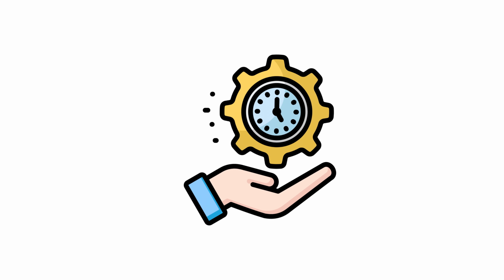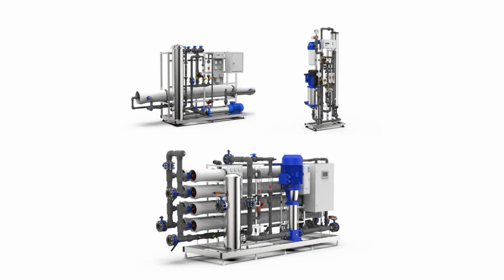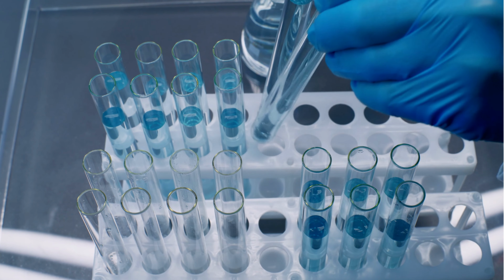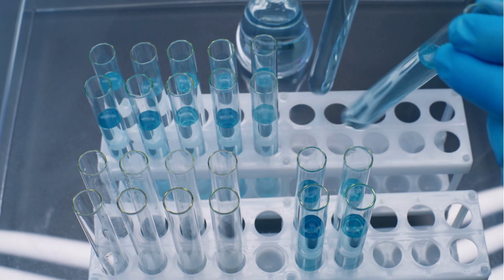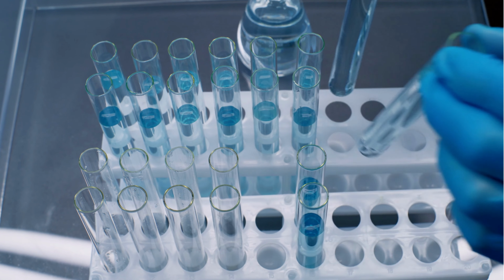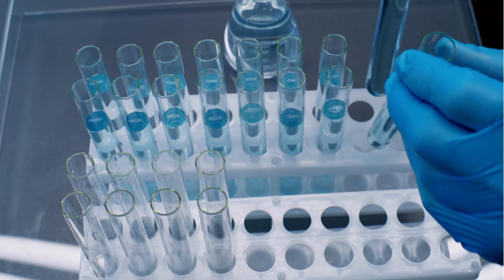This combination is the standard and most effective solution. Reverse osmosis provides deep demineralization and reduces salt content to a level suitable for further treatment, while electrodeionization performs the final purification to ultra-pure parameters, without chemical regeneration, in continuous mode, and with low operating costs.